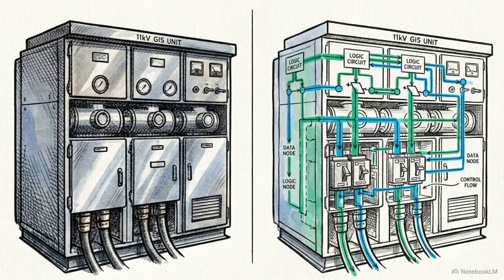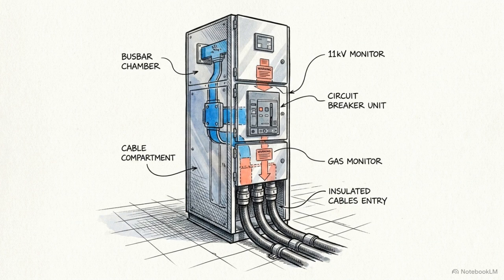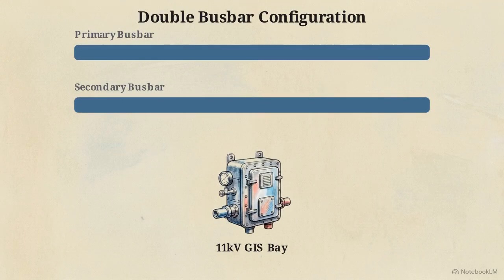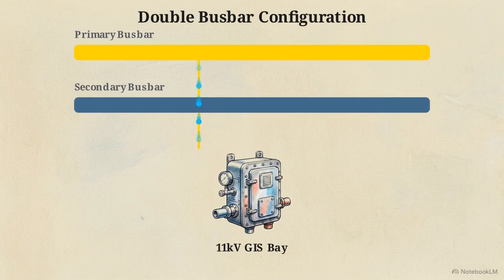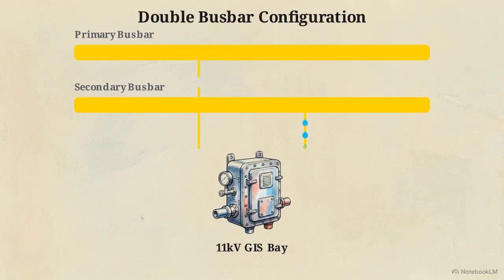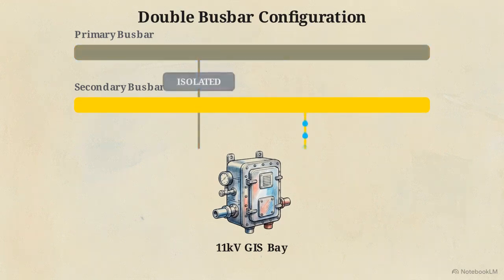Maintaining power during severe grid fluctuations requires precise coordination between the absolute limits of physical switchgear and the dynamic behavior of simulated electrical controls. The structural foundation of this network is a fixed-pattern 11 kilovolt gas-insulated switchgear bay. Looking at this 3D schematic, the defining feature is the double busbar configuration. Two isolated conductive layers run parallel. Operators can route energy through the primary busbar, then instantly divert flow to the secondary layer, isolating the primary bar for maintenance without dropping load.